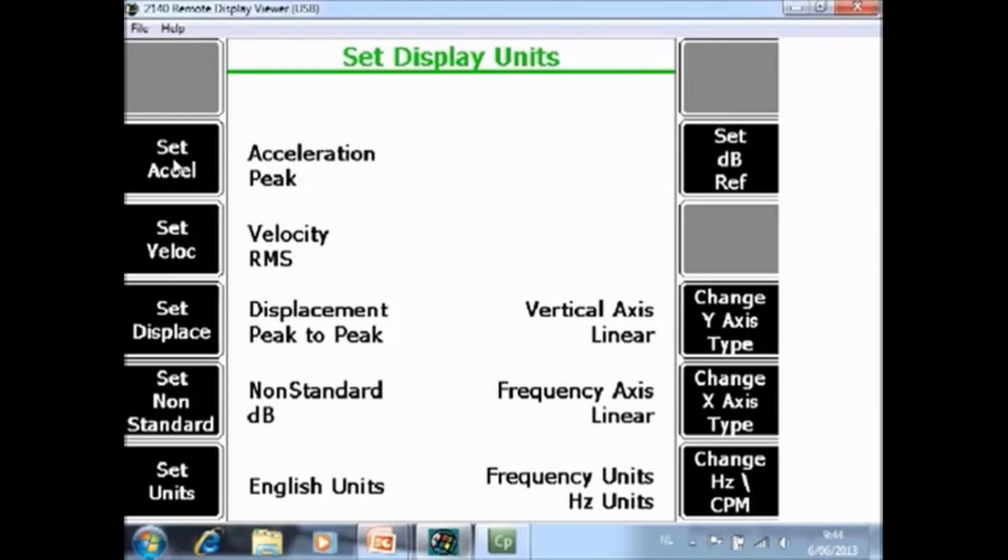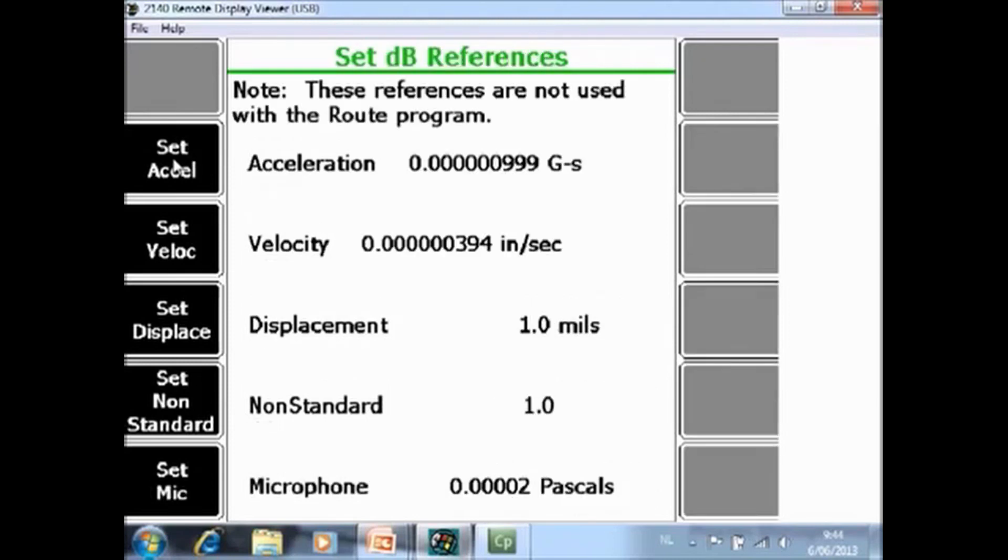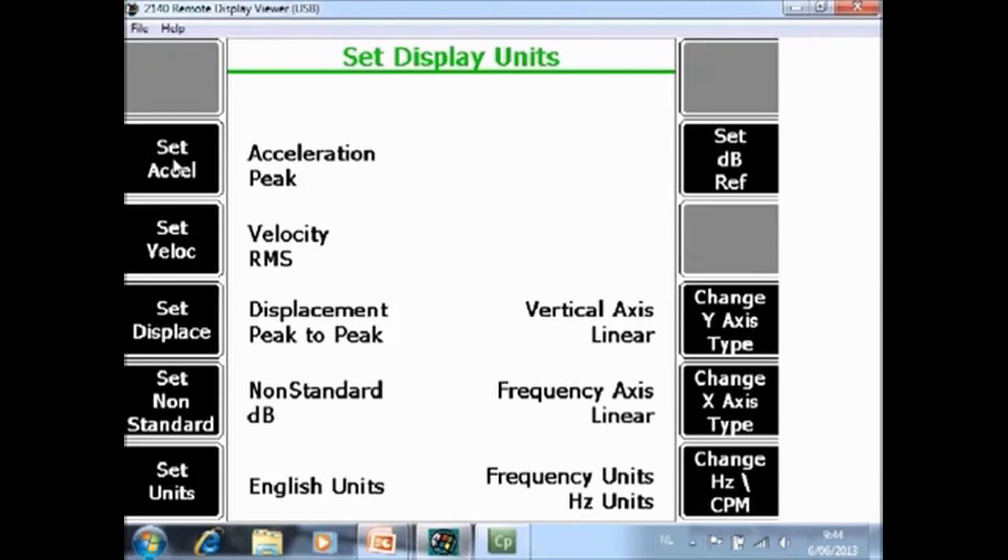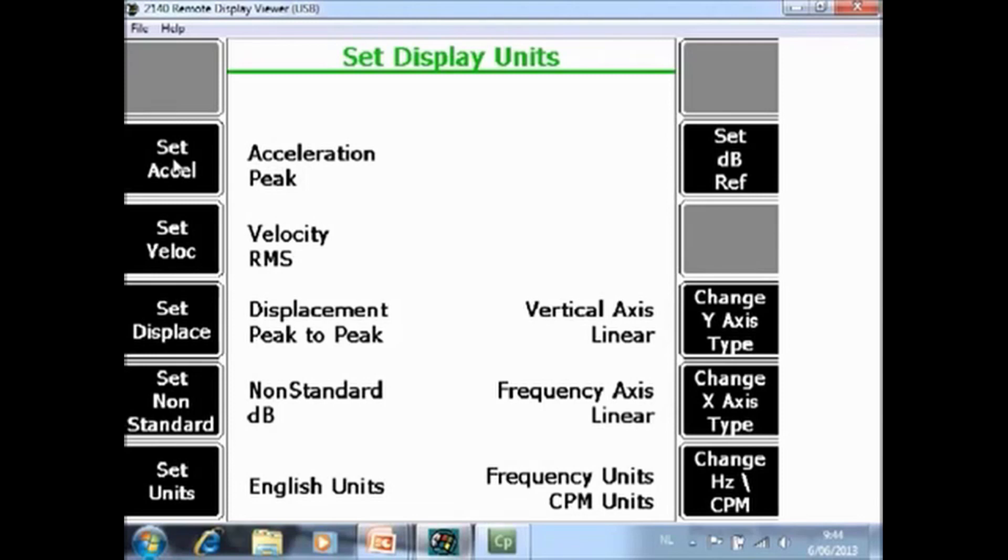F8 set dB ref. Here you can change the reference values for your acceleration, velocity or displacement data. F10 change Y axis type. You can have the Y axis displayed linear or log. F11 change X axis type linear or log. And F12 is to change between frequency units in hertz or in CPM.